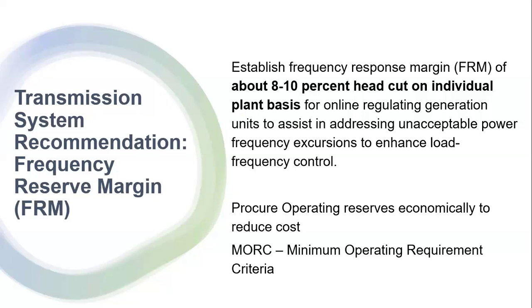So every normal system operates under this MORC, your minimum operating requirement. So I'm operating, serving my load, and all of a sudden I lose a transformer. Am I able to serve the load? It is on that basis that you procure the operating reserves in megawatt equivalent.